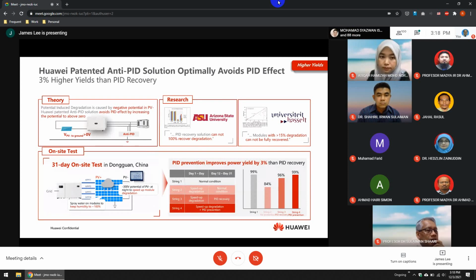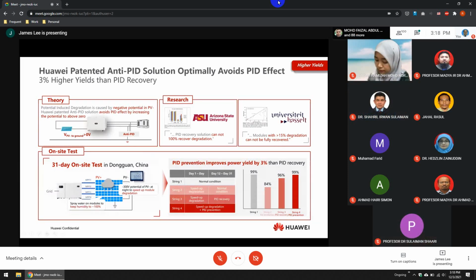But for us, we actually have PID prevention - this is for large scale, of course. For our rooftop, we have PID recovery. The reason is because of the type of earthing system. For our PID prevention or anti-PID system, it is an IT or floating earthing system, whereas for your low voltage connected systems, you would have a neutral line which does not enable this kind of PID recovery or PID prevention.